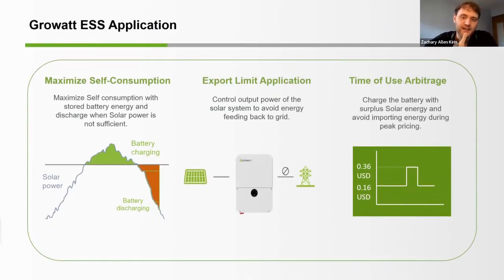So the hybrid functionality of the MIN device is proven to maximize your customer's self-reliance on stored renewable energies. Charging the battery with solar energy during the day and discharging to the customer loads during the night is the default setting of the inverter, the maximize self-consumption mode. This is allowing your customers to rely solely on the renewable energies and the system that they paid for. This is the most important part of the modes that we are offering. Maximize self-consumption is very, very important.